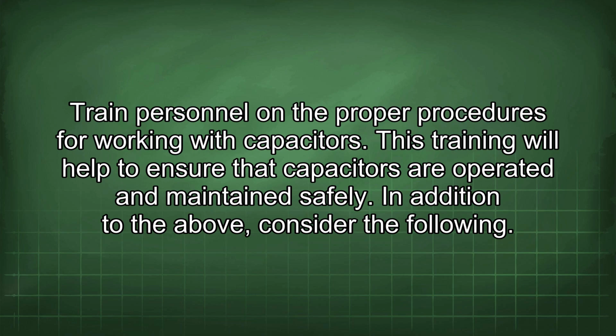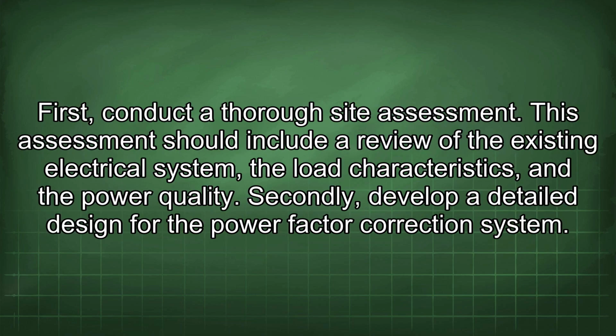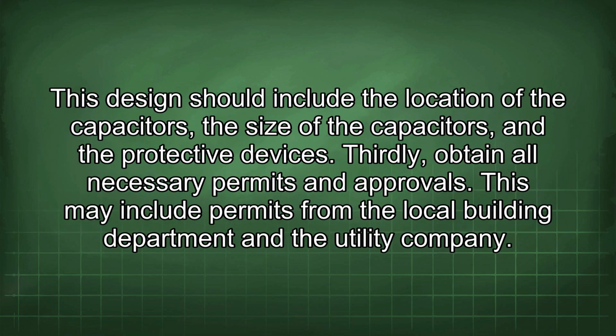In addition to the above, consider the following. First, conduct a thorough site assessment. This assessment should include a review of the existing electrical system, the load characteristics, and the power quality. Secondly, develop a detailed design for the power factor correction system. This design should include the location of the capacitors, the size of the capacitors, and the protective devices. Thirdly, obtain all necessary permits and approvals. This may include permits from the local building department and the utility company.